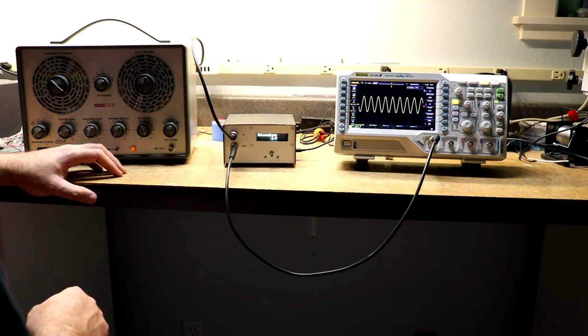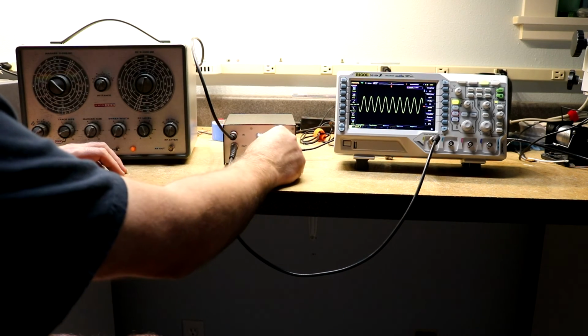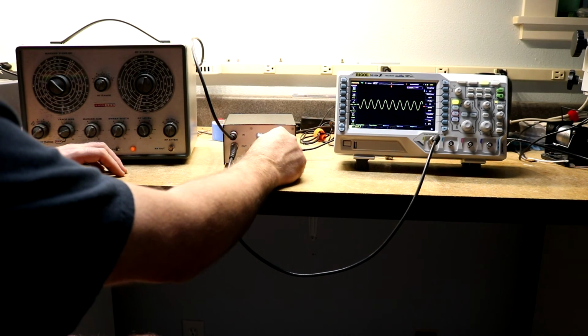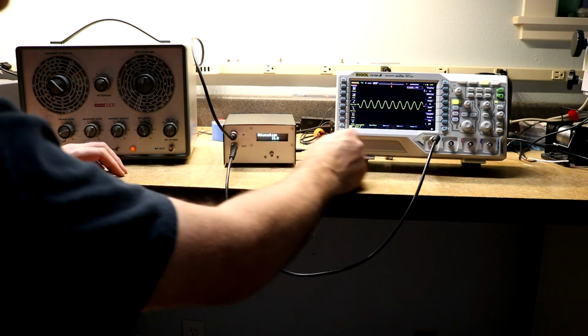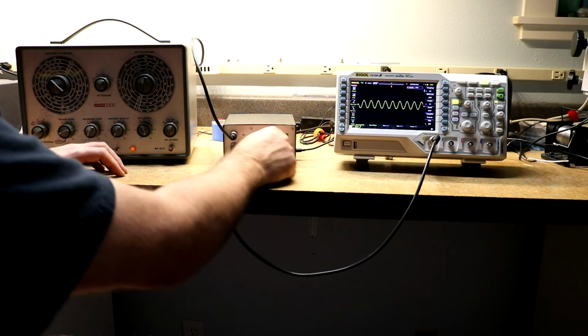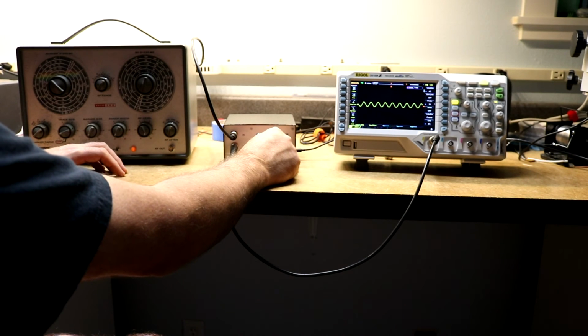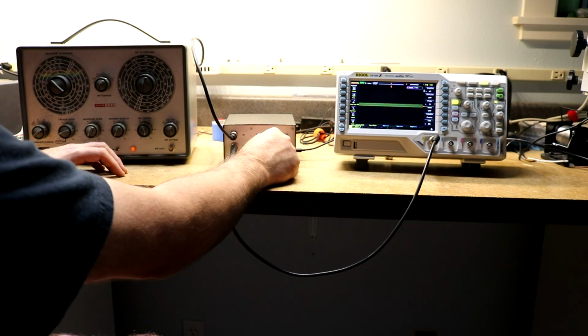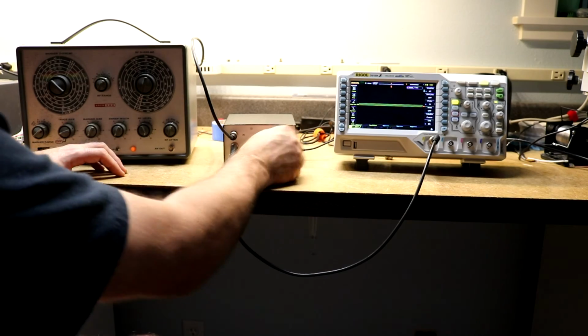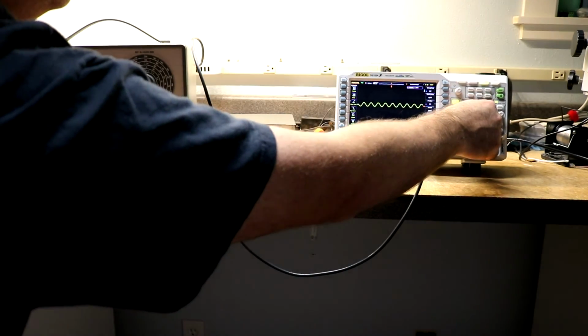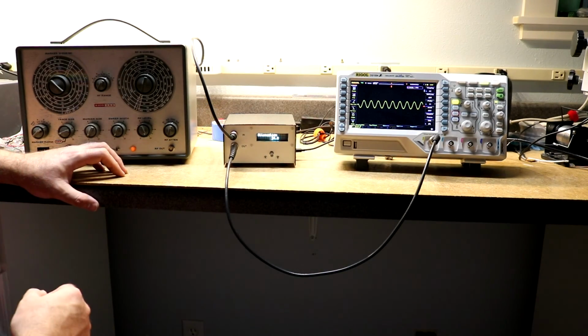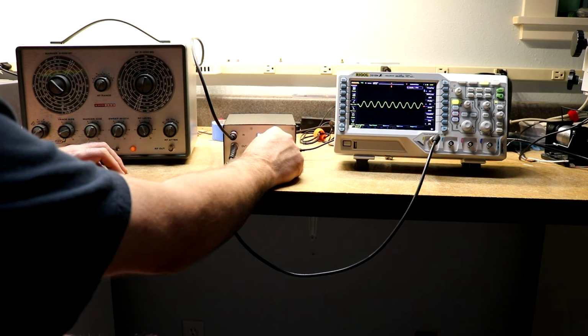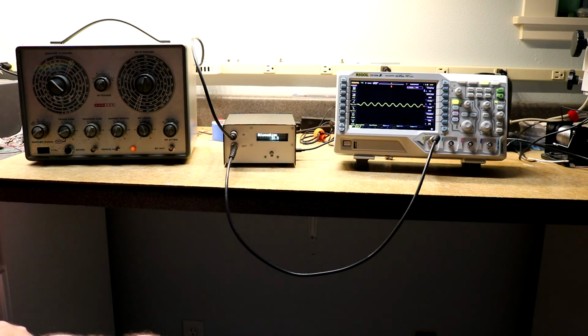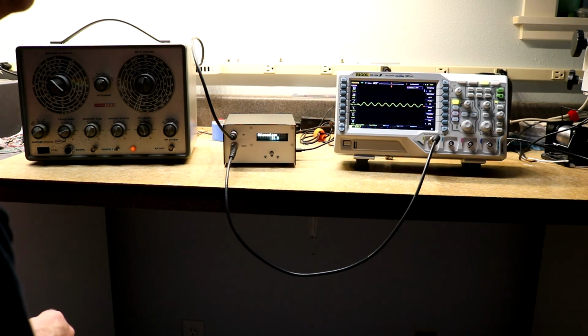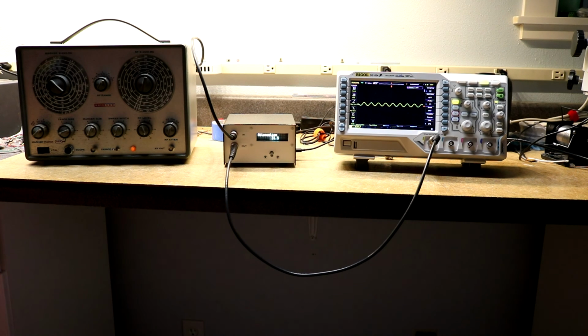So there's 6 decibels, we've got about half the signal, about 640 millivolts. 12 decibels should bring us down to about a quarter, about 328 millivolts. 24 decibels brings us down to about 75 millivolts. And our top end here at 31.5 decibels of attenuation, bringing us down to about 34 millivolts.